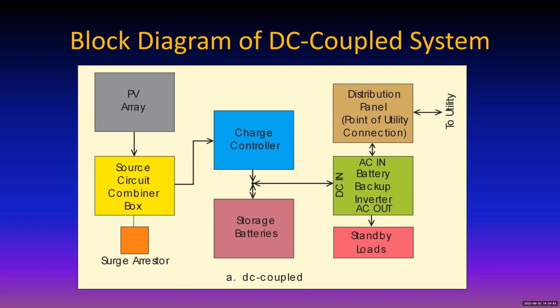The DC coupled system has one inverter, and it's a very versatile inverter that can operate as a current source when the utility is live, and it'll operate as a voltage source and disconnect automatically from the utility if the utility goes down. And then, even though it disconnects, it continuously monitors the utility, and when the utility comes back up again, it waits 5 minutes, makes sure the utility is stable, and then starts delivering back to the utility if the utility wants it.